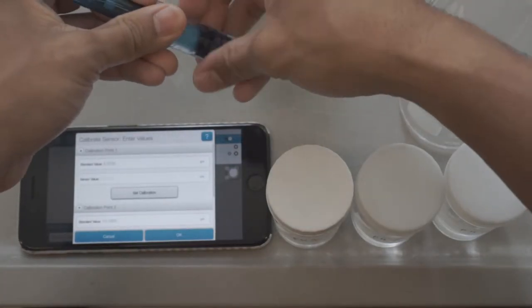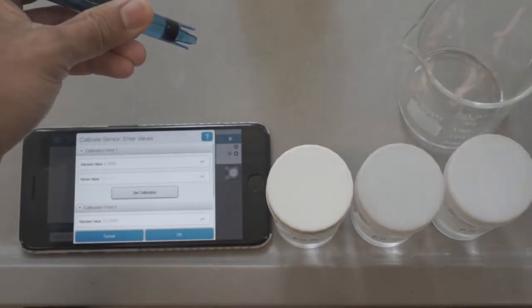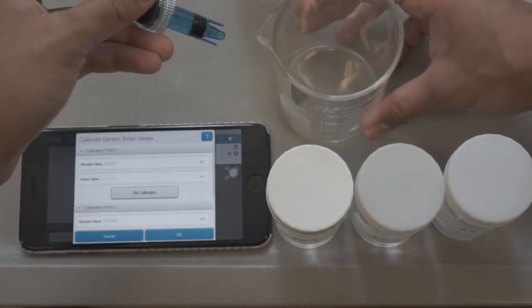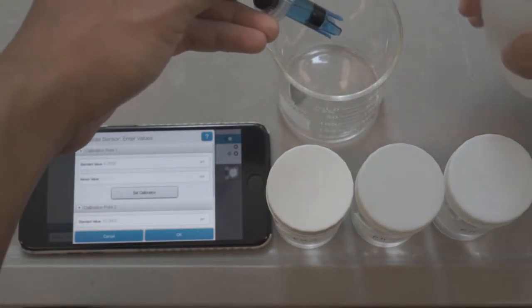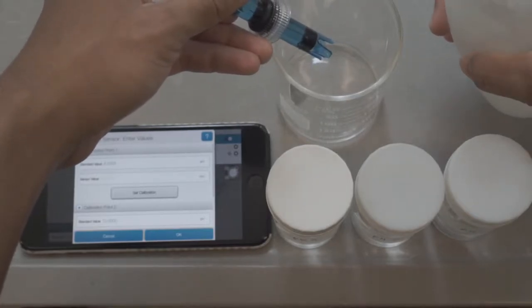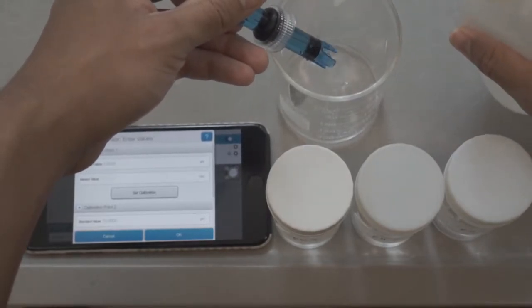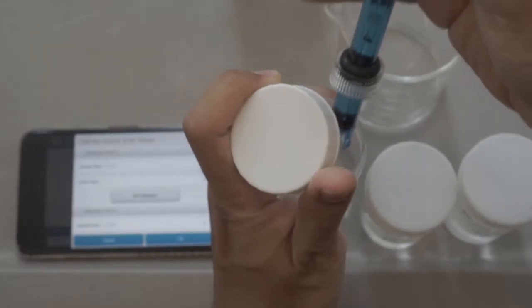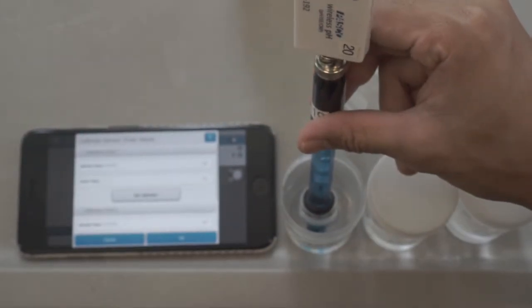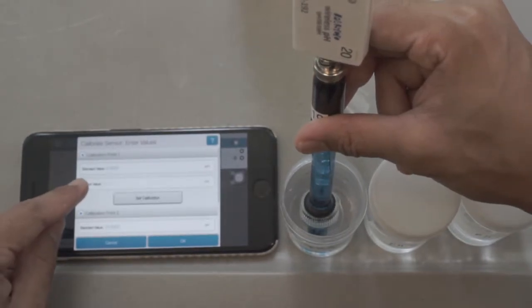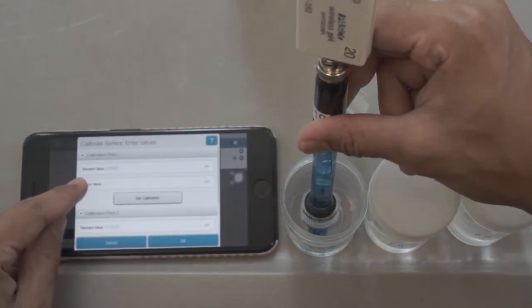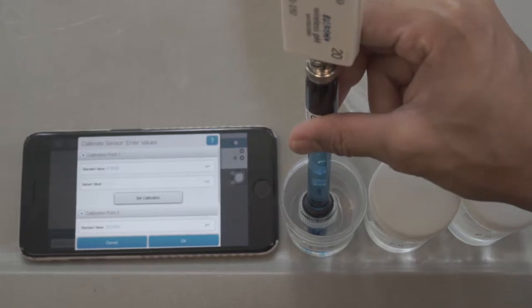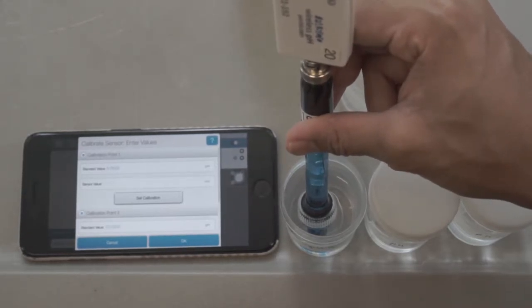Next, remove the bottle covering the probe by unscrewing it. Next, wash the end of the probe with distilled water. Dip the end of the probe into the pH 4 solution. Keep an eye on the sensor value under pH 4. Once it has stabilized, press Set Calibration.